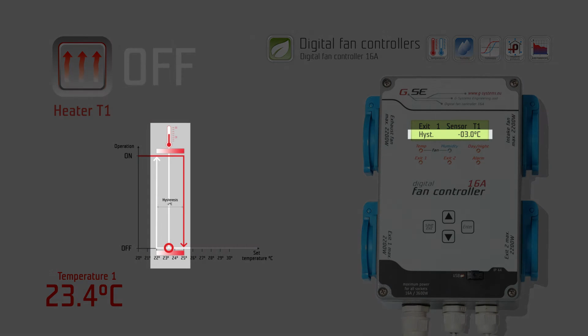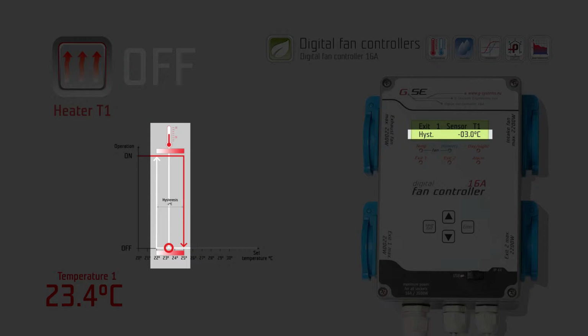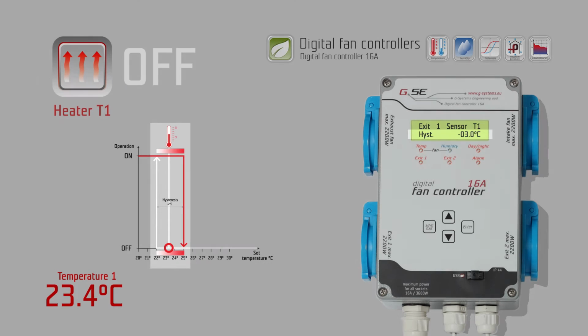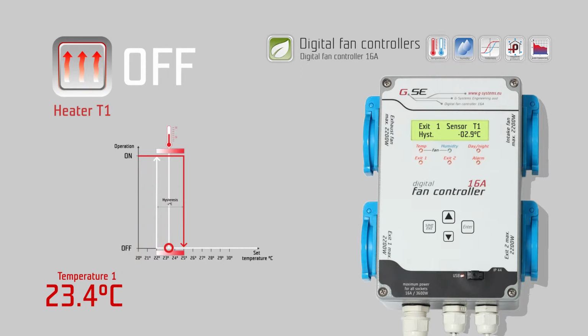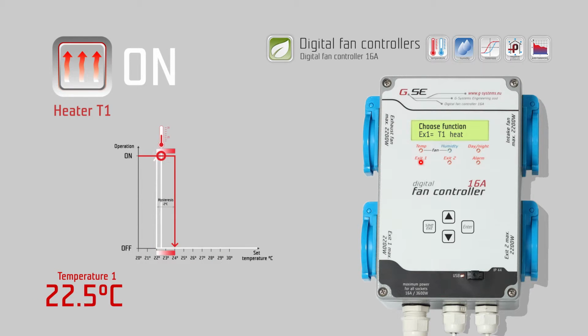The hysteresis determines the quiescent condition of the contact. If the hysteresis is set to -2 degrees Celsius, and the day temperature is set to 24 degrees Celsius, then the heater will switch on at 22 degrees, and switch off when it rises to 24 degrees. This contact will remain off until the value drops below 22 degrees Celsius.